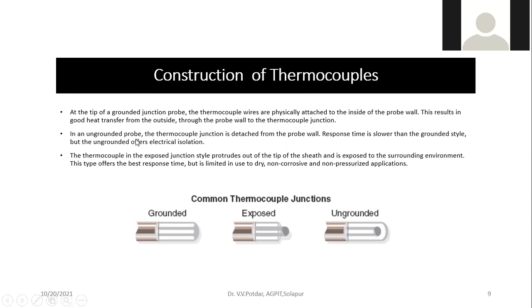In an ungrounded probe, the thermocouple junction is detached from the probe wall. See, the thermocouple junction is detached from the probe wall. Response time is slower than the grounded style, but the ungrounded junction offers better electrical insulation. Response time is slow. Grounded junction thermocouple gives me quick response, whereas ungrounded thermocouple junction gives me slow response.